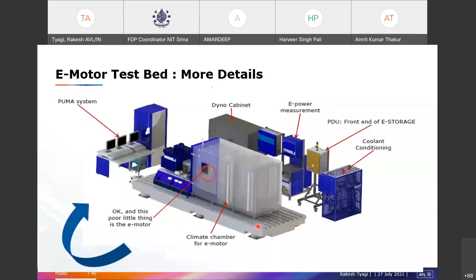When it comes to the base, you see 4 or 6 air valves, because when you are running this at 20,000 rpm, there is a chance that heavy vibrations can be generated. These vibrations should not affect performance or pass to the other testing area, so generally air cushions are used here. Whenever testing starts, this base plate will be on air cushions and no vibration is transferred to other areas. These vibration dampers take care that your vibrations don't go too high.